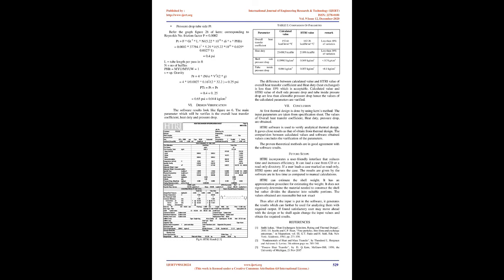Design Verification. The software results look like figure number 6. The main parameters which will be verified are the overall heat transfer coefficient, heat duty, and pressure drop. The difference between calculated value and HTRI value of overall heat transfer coefficient and heat duty (heat exchanged) is less than 10% which is acceptable. Calculated value and HTRI value of shell-side pressure drop and tube-side pressure drop are less than allowable pressure drop hence the values of the calculated parameters are verified.